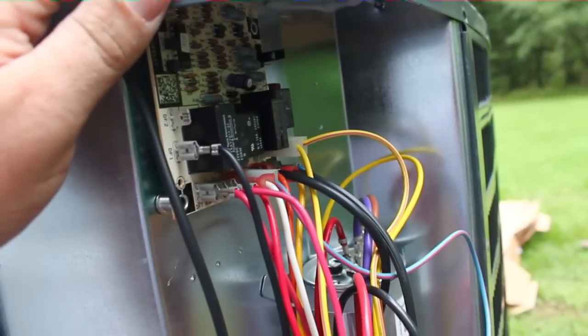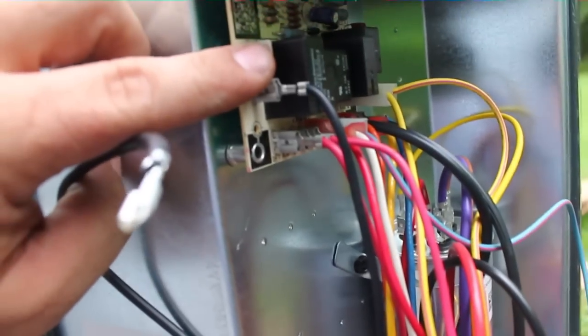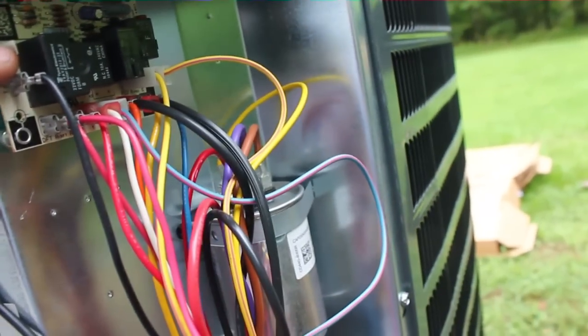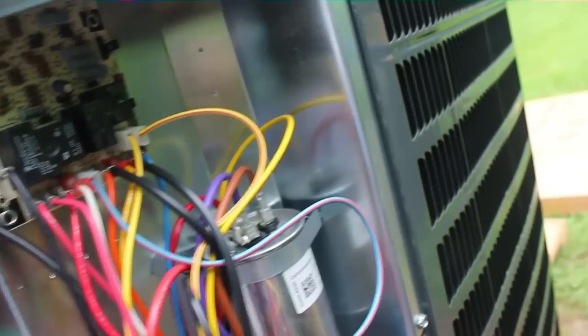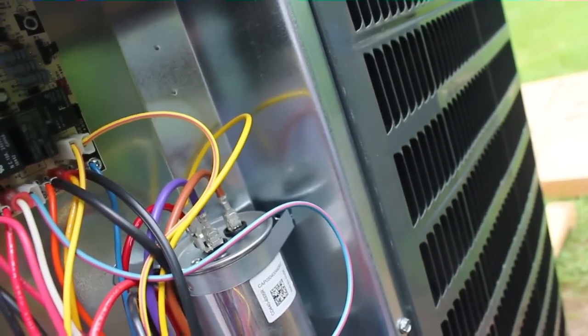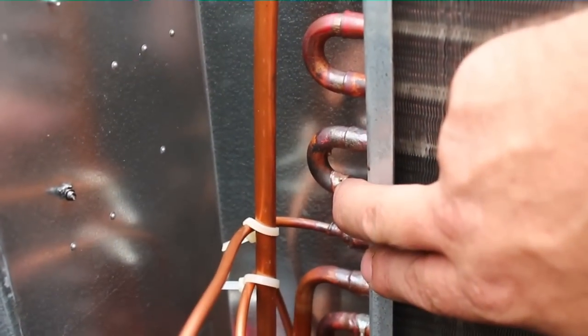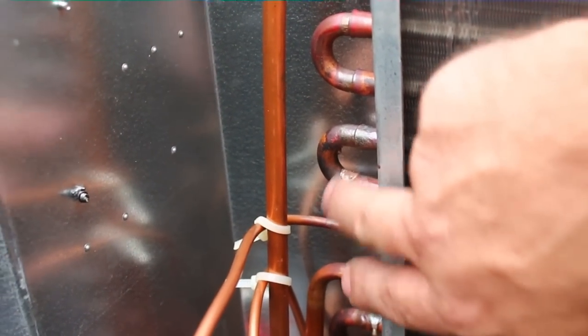We're going to take the top off the unit now, so we have to take the 3 wires off the fan motor. Have the black wire disconnected off the defrost board here. We'll take the other 2 off the capacitor. We see our brown and purple wires. We'll take those off, then feed them back down through the hole here, and we'll be able to pull the top off. If we look at this U-bend right here, you will see that it is leaking.